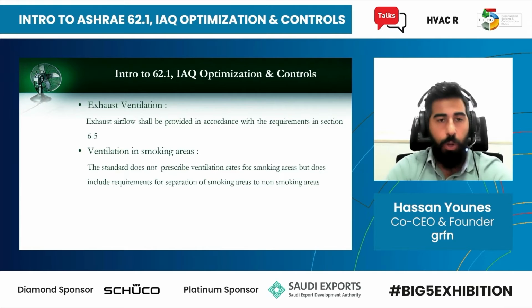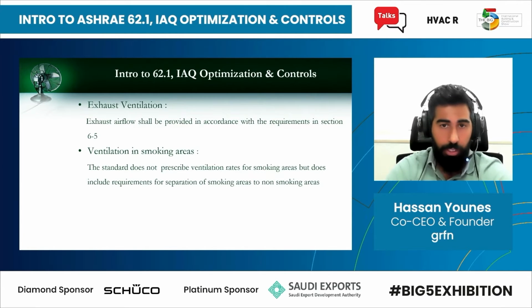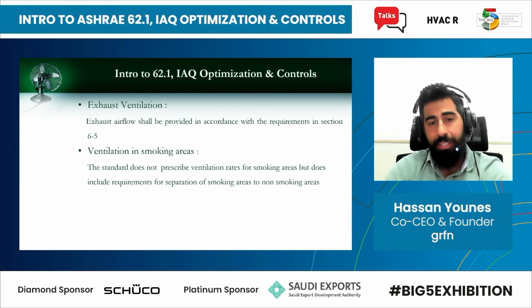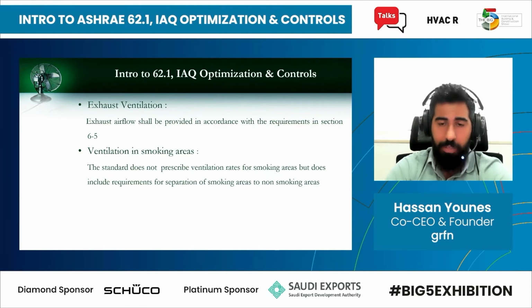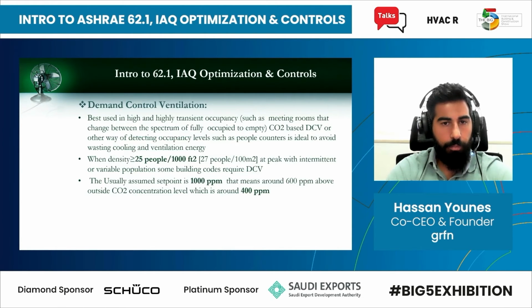Exhaust also is required. Some specific rooms, even if you're doing natural ventilation, need to have mechanical exhaust, like toilets, kitchens, and so on. Normally it's taken from that particular table. Ventilation in smoking areas: the standard does not prescribe ventilation rates for smoking areas, so for a smoking zone you won't be able to find the required outside air per person. It's not part of the standard. It just says it should be more, but it does not say how much. Basically, it's up to the user or the jurisdiction to give the consultants the requirements of how much outside air is required.